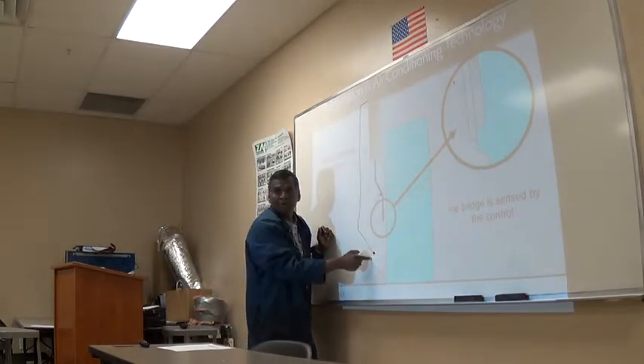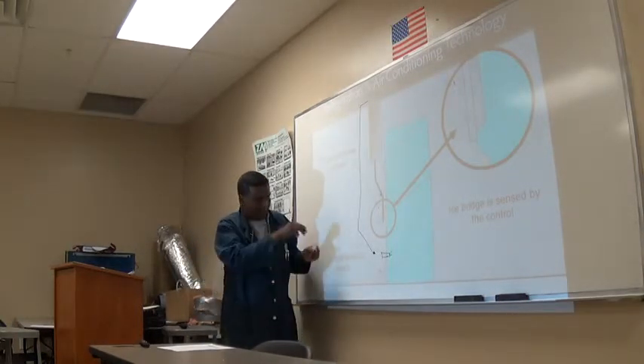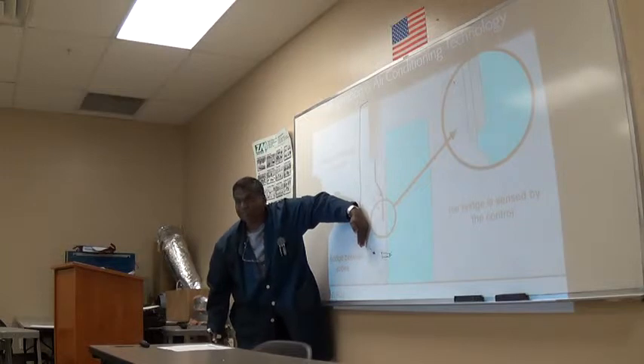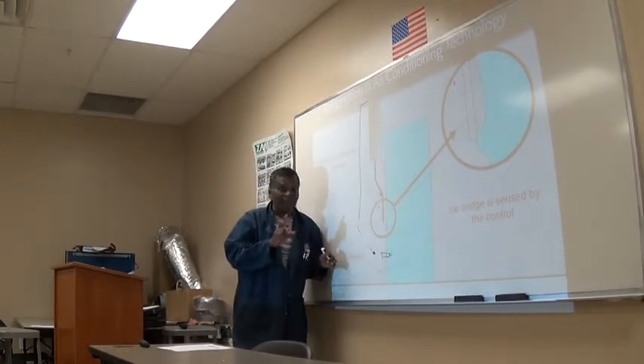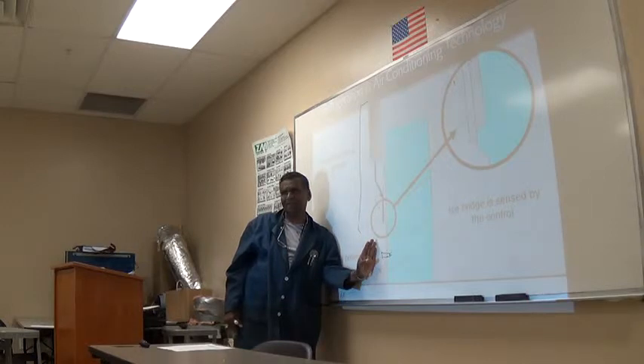When the ice making cycle is done, this switch closes. When the ice drops off, it slides out, opens this, and goes down. It breaks that contact and signals the board, 'I just dropped the ice here.' If this stays like that, the board is going to go back into ice making cycle for at least one minute. If it does not see this close back, it's going to shut down the machine because it will figure ice is stuck here, meaning the bin is full.